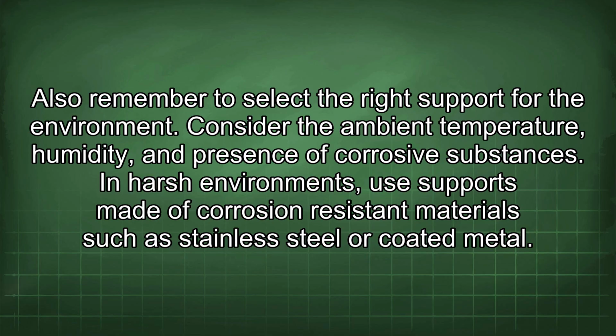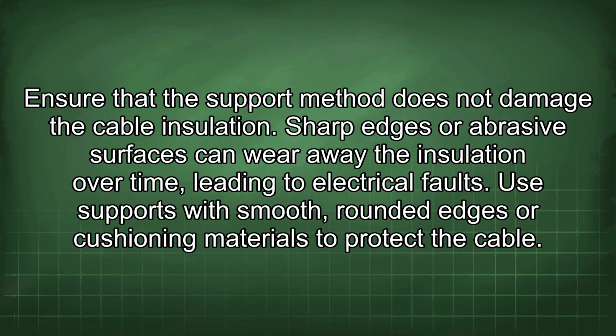Also remember to select the right support for the environment. Consider the ambient temperature, humidity, and presence of corrosive substances. In harsh environments, use supports made of corrosion-resistant materials such as stainless steel or coated metal. Ensure that the support method does not damage the cable insulation. Sharp edges or abrasive surfaces can wear away the insulation over time, leading to electrical faults. Use supports with smooth, rounded edges or cushioning materials to protect the cable.